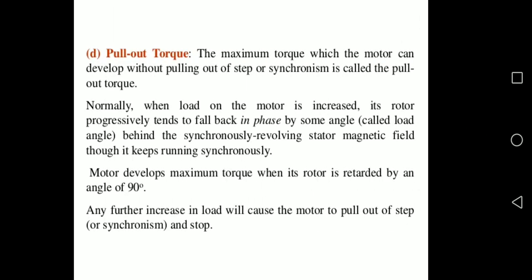Pull-out torque is the maximum torque which the motor can develop without pulling out of synchronism. The angle between the stator field axis and the rotor field axis is called the load angle alpha.